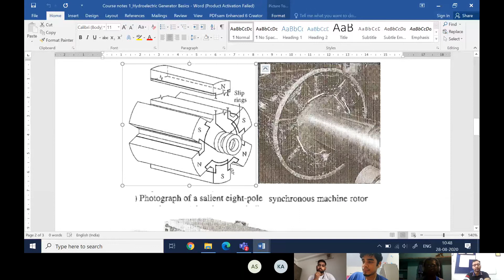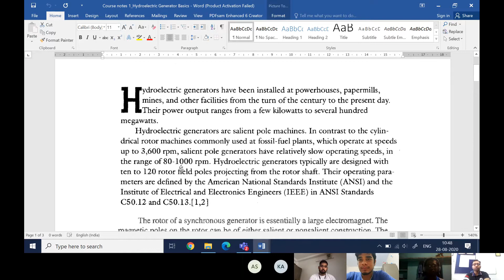Now we can read this paragraph. It says that hydroelectric generators are salient pole machines. So hydroelectric generators are always, invariably, having this salient type construction, in contrast to the cylindrical rotor machines commonly used at fossil fuel plants. The cylindrical rotor machines are typically used in coal-based or thermal power plants, which operate at speeds up to 3600 RPM. So the cylindrical rotor machines can have a very high speed, up to 3600 RPM, whereas salient pole generators have relatively slow operating speeds in the range of 80 to 1000 RPM.